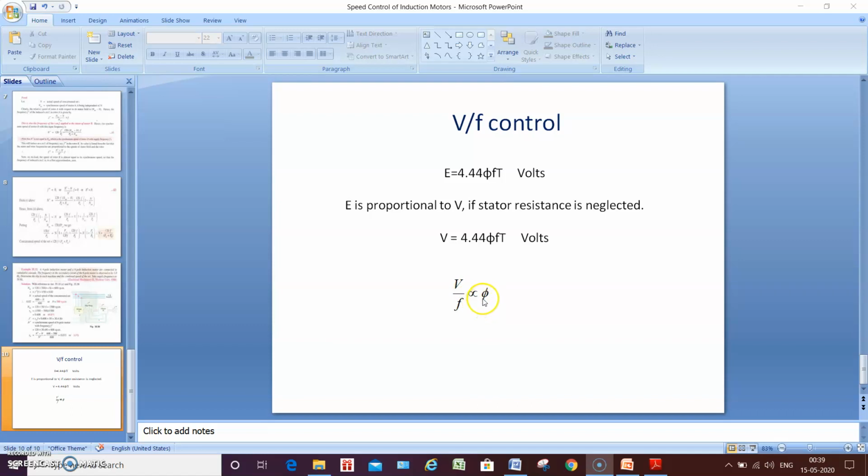It will end with the harmful effects on the induction motor. The torque ripple and many more drawbacks will be there. We are not going to discuss them in detail now. But anyhow, the magnetizing current will be increasing, so the source current and voltage will get distorted, or harmonics will be introduced into the source current as well as the voltage. So it will produce core losses and copper losses. Another drawback is that the acoustic noise or EMI noise will be increasing.